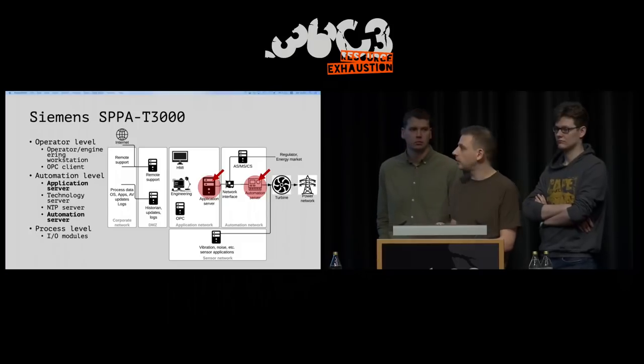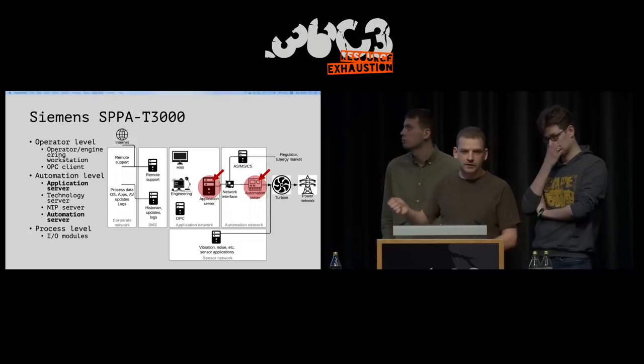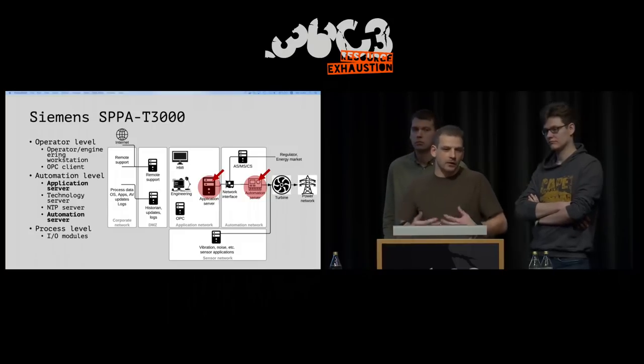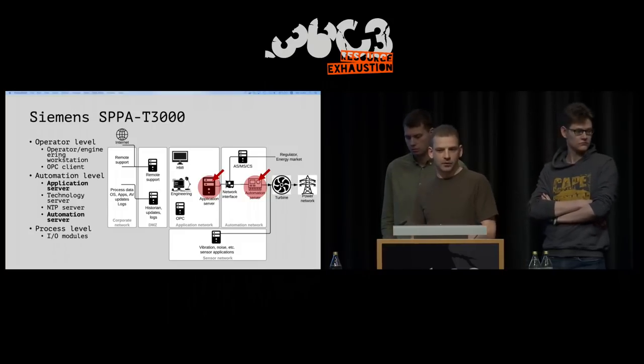Despite the fact that if you read the manuals for these Siemens systems, there are a lot of different networks and highways, and Siemens states that there is no connection between the application network and external networks. In practice and in reality, you will find things like a specific sensor network monitoring vibration, foreign objects, and noises inside the turbine. You will also find a demilitarized zone, because power plant operators generally won't have on-site maintenance engineers, they try to do remote support.